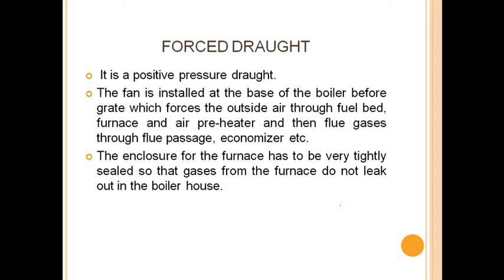Forced draught is a positive pressure draught. The fan is installed at the base of the boiler before the grate, and it forces the outside air through the fuel bed, furnace, and air preheater, and then the flue gases through the flue passages, economizer, etc. The enclosure of the furnace is very tightly sealed so that gases from the furnace do not leak out into the boiler house.